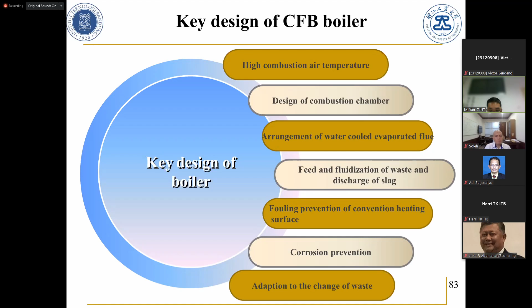So we use high temperature air, or high temperature primary air, to ignite the waste, and we make the furnace temperature high enough, over 850 centigrade, staying for 2 seconds. So the temperature of the primary air is very important to ensure the combustion temperature, which is also a prerequisite for the clean and efficient operation of the furnace. Here you can see that as the primary air temperature increases, the furnace temperature also increases. At 250, the furnace is 800. Of course, the MSW heat value is lower, only 950 kcal per kilogram. Now, the low heating value of MSW in China is roughly 1,500. It has improved significantly.